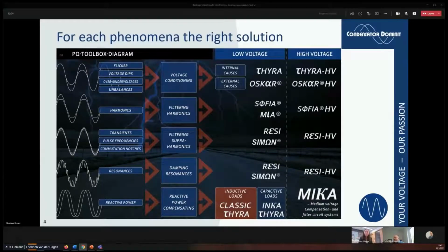Now, this kind of harmonic, if the voltage distortion, for example, is above 8%, normally we experience serious failures in the machine park, and also a loss of warranty from the side of your suppliers. If you have a harmonic issue in your company, the supplier is out of warranty of any machine.